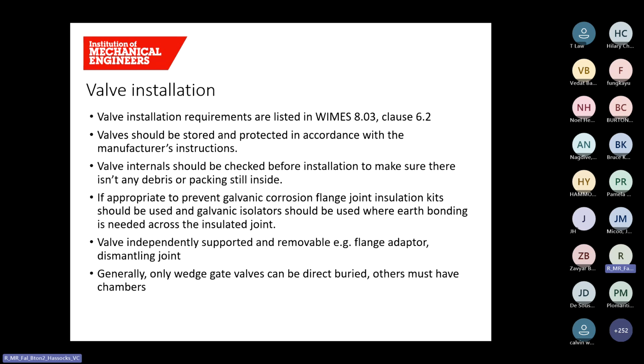When designing a system, the installation type needs to be considered as well. For example, valves and pipelines can be installed within a building or located outside in a coastal environment. Some valves, typically wedge gate valves, can be installed directly in the ground or within a below ground chamber. Installation guidance is available in WIMES 8.03. Before being installed, valves should be stored safely to protect them from damage or contamination. And when they are installed, the internals should be checked to make sure there's no debris or remnants of packaging.